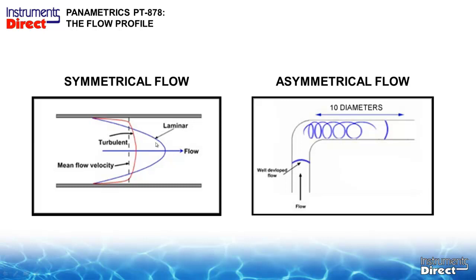Whether they're more blunt or elliptical doesn't make that much difference to us, but what does make a difference to us is that if you draw a center line down this pipe, the top half of flow would equal the bottom half of flow. So in that case, symmetrical flow profile, which in this particular diagram in your 10 to 5 or 15 pipe diameters, is also based upon flow rates that are around 10 feet per second in velocity. Higher flow rates, more straight run of pipe. Lower flow rates, less straight run of pipe.